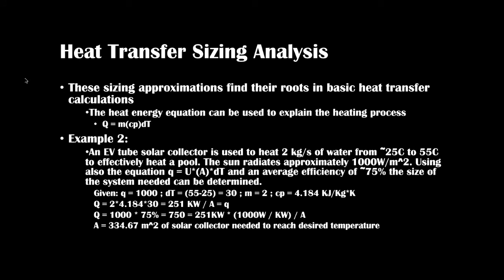These sizing approximations actually find their roots in basic heat transfer calculations. The heat energy equation, being mass flow rate times heat capacity times the temperature out minus the temperature in, can be used to explain the heating process. An example is shown below in which an EV tube solar collector is used to heat 2 kilograms per second of water from 24 degrees Celsius to 55 degrees Celsius to effectively heat a pool. The sun radiates approximately 1,000 watts per meter squared. Using this and also the equation Q equals the overall heat transfer coefficient times area times the change in temperature, and an average efficiency of 75%, the size of the system needed can be determined. The pump can then be cycled to maintain the desired temperatures.